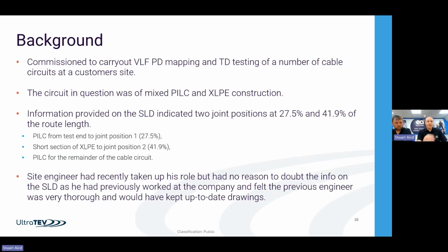This particular one we're going to talk about today has mostly paper insulated cable. Paper insulated cable historically would have partial discharge, little voids all the way along it where you've got wraps of cable going around, and if they've got wax and stuff in there, it'll generally be okay for long periods of time. But then with XLPE, over the years, there's been a failure in the cable, so areas get replaced with new modern XLPE cable, which isn't very tolerant to partial discharge at all. If you get PD in that section, it's going to fail in quite a short period of time.